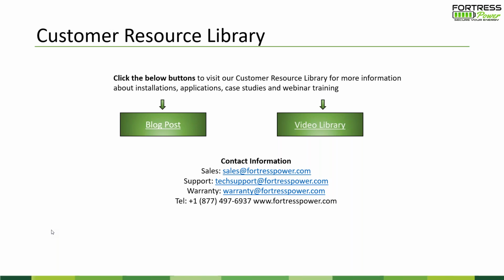What's the point of connecting the communication cable between the eVault and the inverter if it doesn't support closed loop communication? It does support closed loop communication. We went through a period where we were still changing up the control boards on our various products on both sides of the manufacturer end. We originally intended the eVault to have closed loop communication with the Sol-Ark, and it's now officially supported for up to 2 eVaults in closed loop. If you're not doing closed loop — say you have a 12 eVault installation — then there's no point in connecting the communication cable.